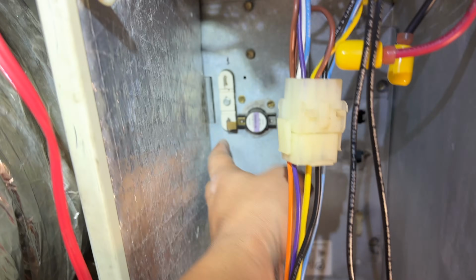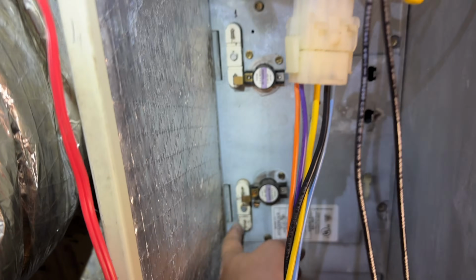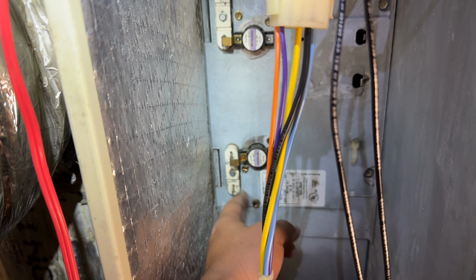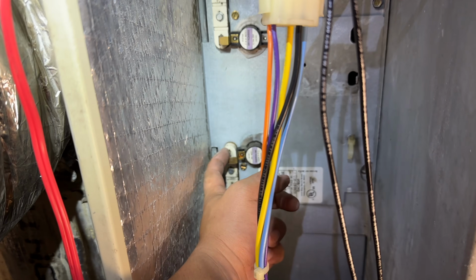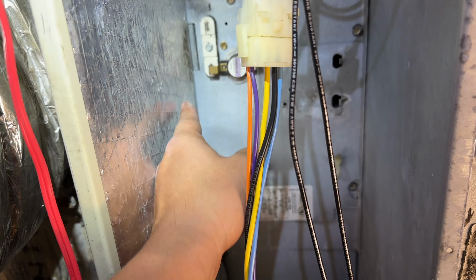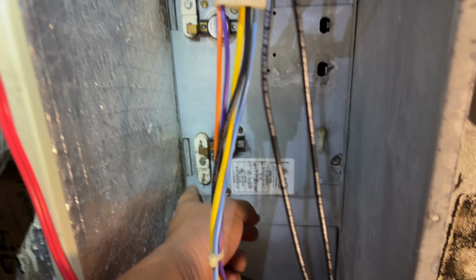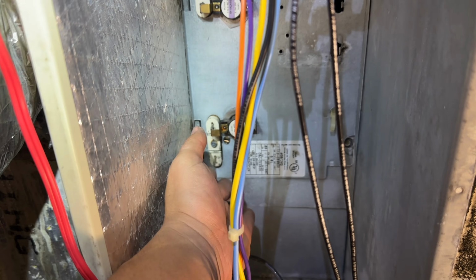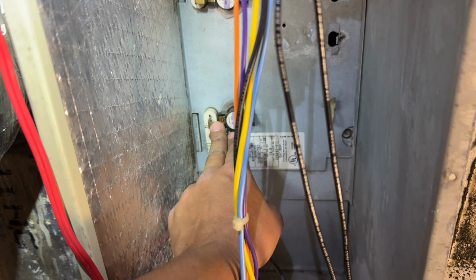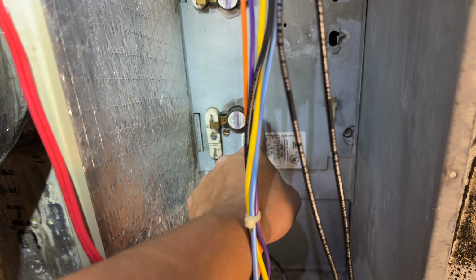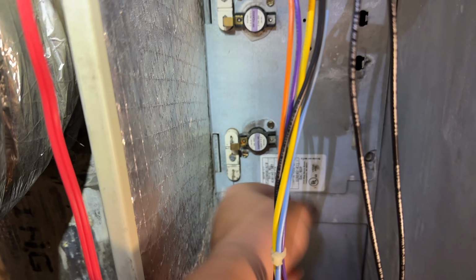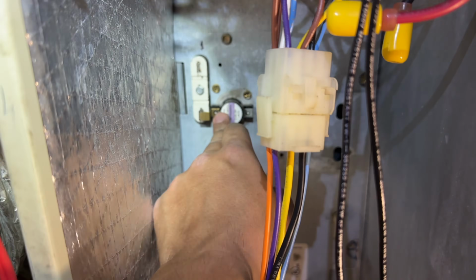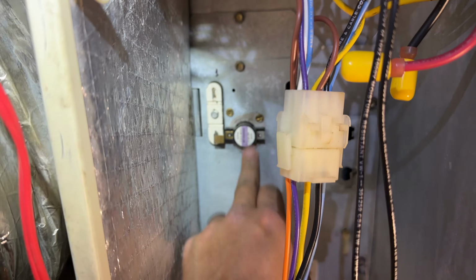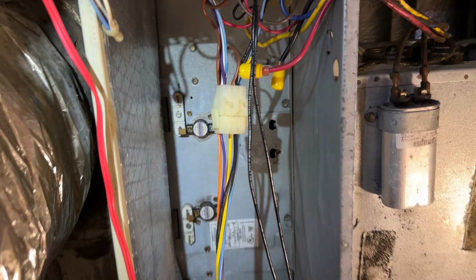It's a little bent from me pulling on it, but the way I checked the heaters is, this is one end, this is the other end, so it's pretty much just a giant loop. So from here to here had continuity, and then to check this, you check here to here. That limit switch is good. Same thing, checked here to here for the heater, and here to here for the limit switch. See, that's good too. So I know the heaters are working.